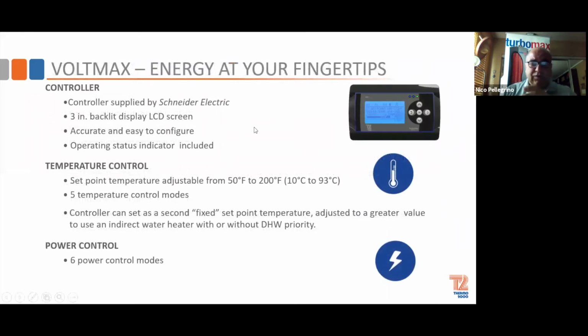So basically, the controller is a Schneider Electric, with our software. It's a 3-inch backlit display. Temperature control is from 50 degrees Fahrenheit to 200, or 93 C, and has 5 temperature control modes. You can also set it on a fixed set point when you use it with domestic hot water priority.